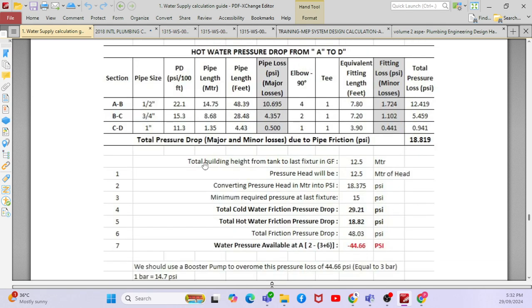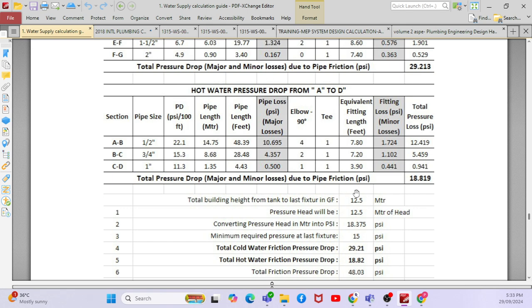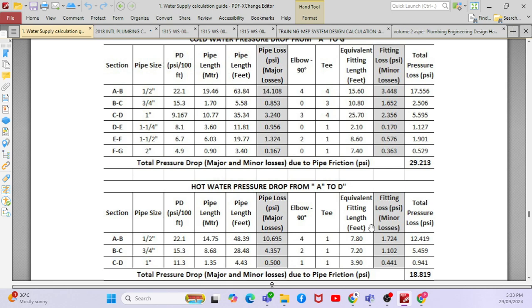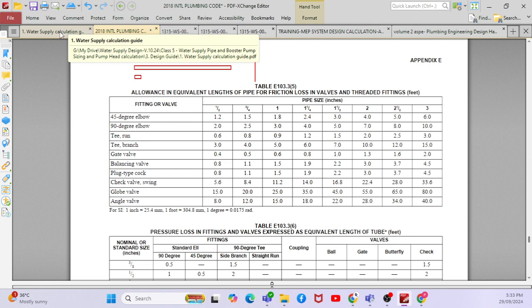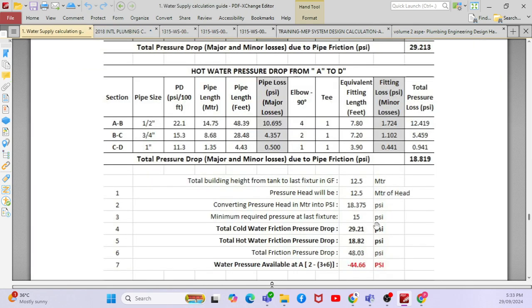The total building height is 12.5 meters — this is the static pressure or static head, so the pressure head is 12.5 meters of head. You convert this value into PSI. Then the minimum pressure required at the last fixture is already given in the IPC standard — there is a chart for each and every fixture showing what pressure is required. That is the minimum required pressure at the last fixture.